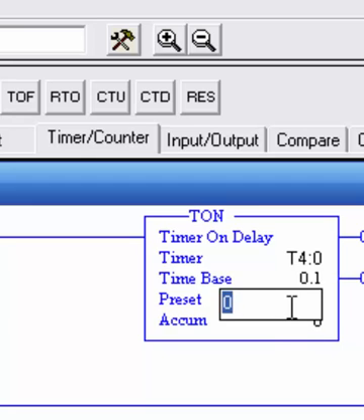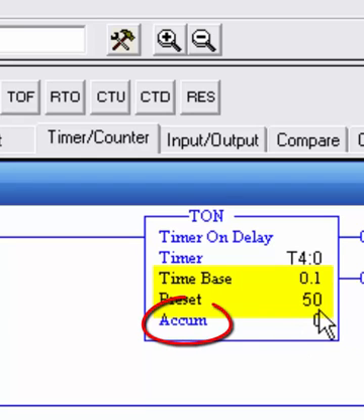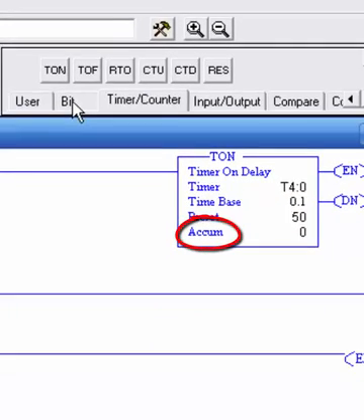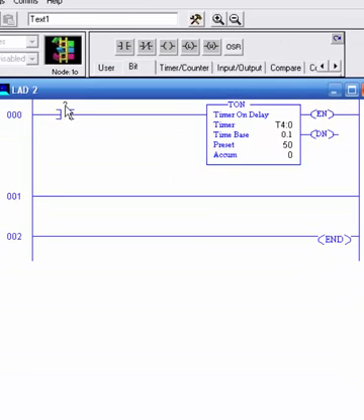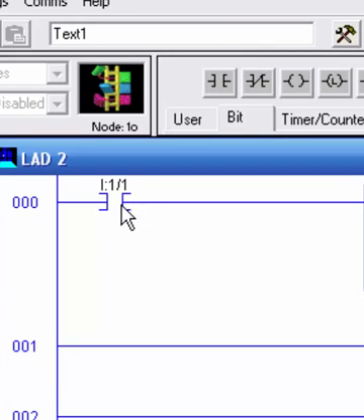Now the preset - let's set this at 50. That'll be 50 tenths, which will be five seconds. As this is timing you'll see the accumulator counting up, and as soon as it hits 50 the done bit goes on. I'll drag an XIC down here and use I:1/1 as the timer enable - when we throw this switch it will enable the timer.